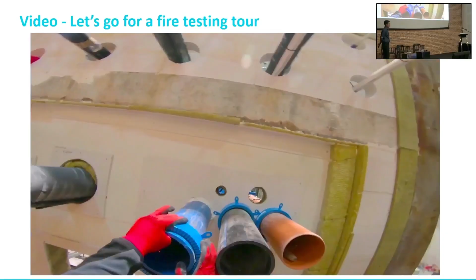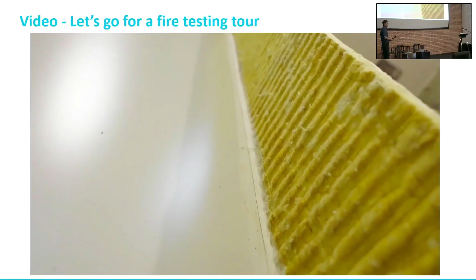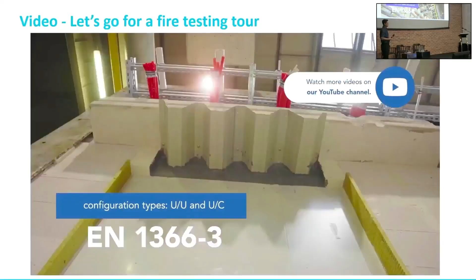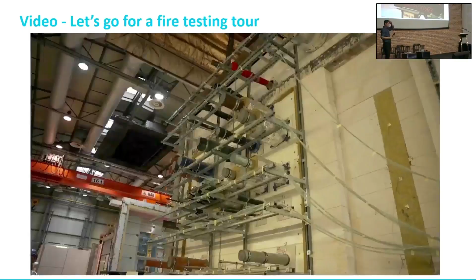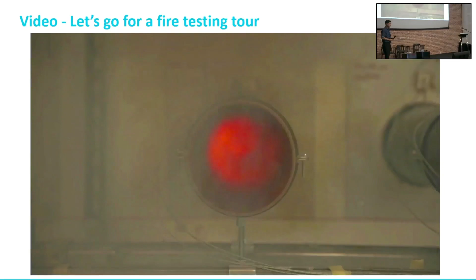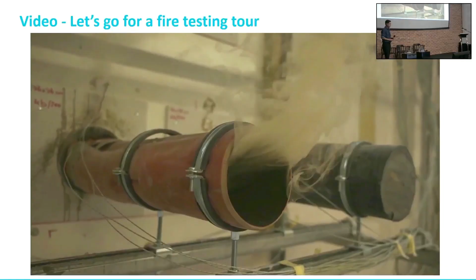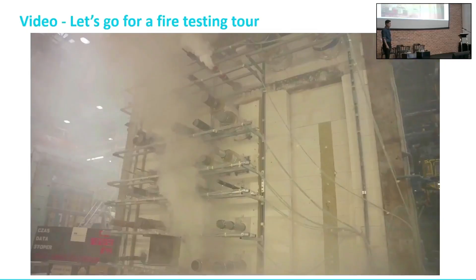The preparation for such a test takes about 50 hours, and the chosen pipe end configurations as well as the placement of the thermocouple must comply with the standards. The test of the PVC pipe is carried out in a UU configuration, that is, ends open in the furnace and outside it, so that fire and high temperatures affect the pipe along its entire length. The plastic pipe softens once it has reached the right temperature, and the fire stop product placed around it in the form of a wrap or collar expands and fills the gaps in the partition once the plastic pipe has burned away. Smoke during this test is normal, as we are not auditing smoke tightness but fire resistance and insulation.